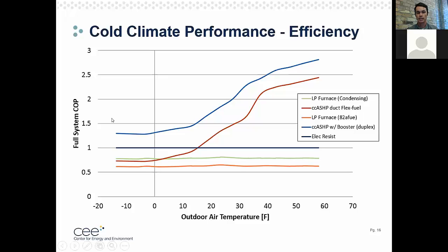So the heat pump continues to operate and move heat from outside to inside and distribute heat for that home. But at a certain point, you're seeing the electric booster come on, which drives this efficiency lower because that's 100% efficient heat. And that's where you see this kind of flatten out. But that heat pump is still delivering heat at as low as -13 degrees where we recorded here. And then the backup heat, the booster, is meeting some of that load as well. So that's why you see a drop below 1.5 when that booster is coming on.